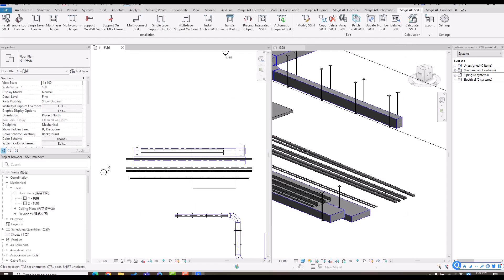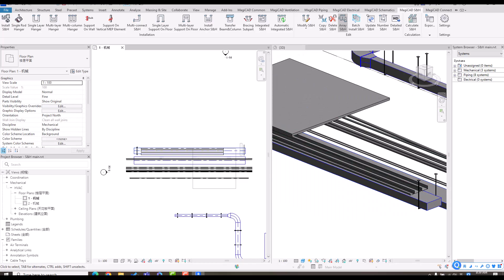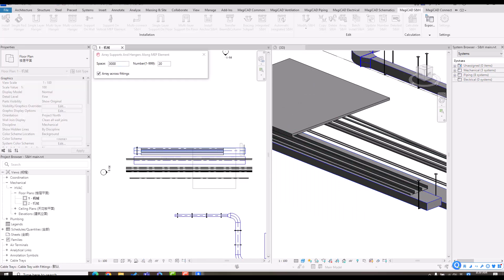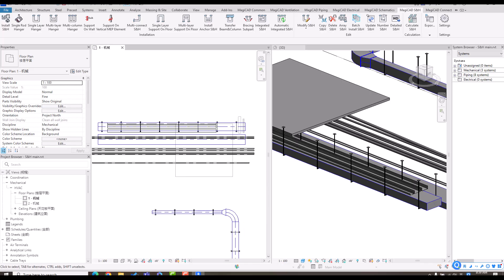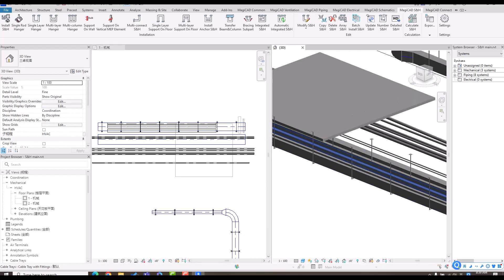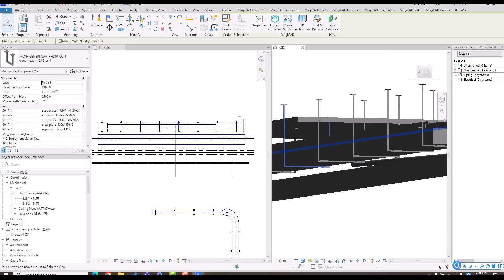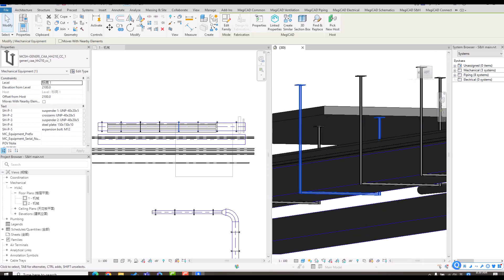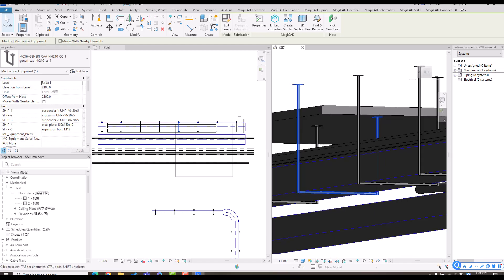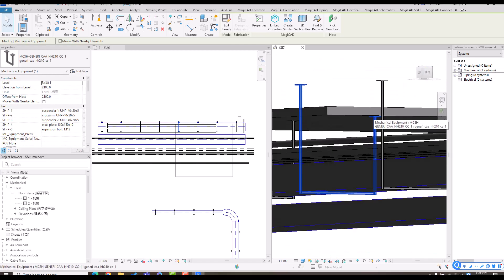Those are some functions about support hanger installation and editing. We also support automatic attachment to slabs or beams. For example, I use the array function and select the direction. Where there is a slab, the support hanger can attach to it automatically. Where there is no slab, it attaches to the top floor or top elevation.